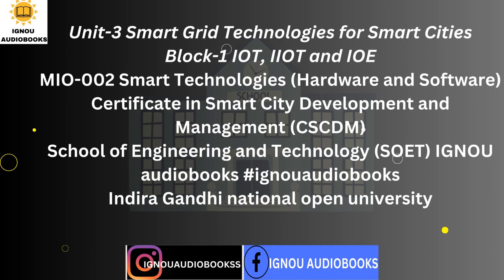SCADA encompasses the transfer of data between a SCADA central host computer and a number of remote terminal units (RTUs) and/or programmable logic controllers, and the operator terminals. A SCADA system gathers information such as voltage, current, circuit breaker status, and relay operation during a fault, transfers this information to the central host computer to indicate that a fault has occurred, carries out control and necessary action, and displays the information in a logical and organized fashion.